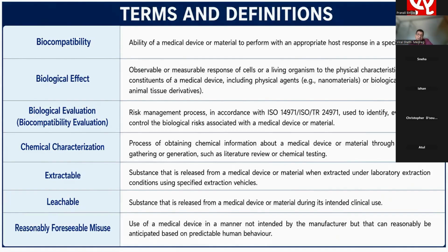So depending on the nature of our devices, we need to follow the different parts. Once you go for the chemical characterization, it talks about extractables and leachables. Leachables are what can be released from your device in clinical conditions, as per the label claim of our device intended by the manufacturer. Extractable means what can be extracted. So leachables are for clinical conditions, and extractables use different laboratory solutions to extract something in an accelerated mode, using different chemicals recommended in ISO 10993 part 12.